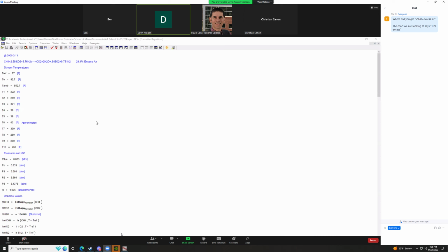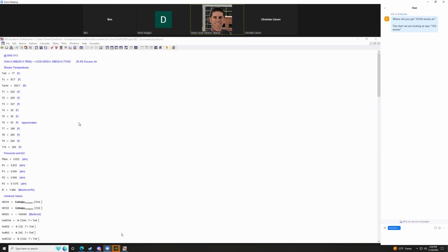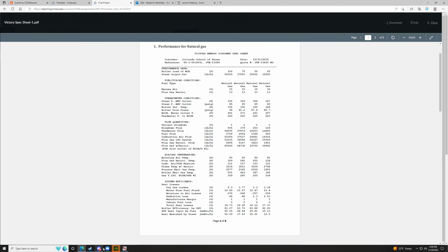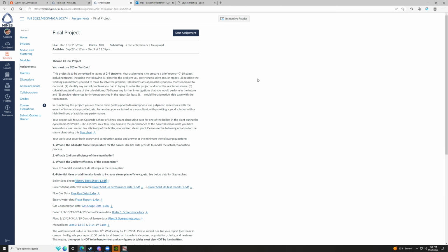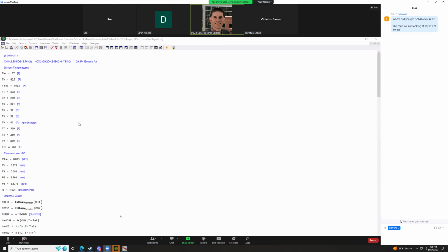Yeah, so one thing I will be interested in seeing is how you get these coefficients here on that part, right? Because you don't have CO, which made me think that you may not have used the flue gas data analysis, right? And the second thing it's showing me is that you're not considering the zone of the flue, it gets brought back to the fresh air, right?